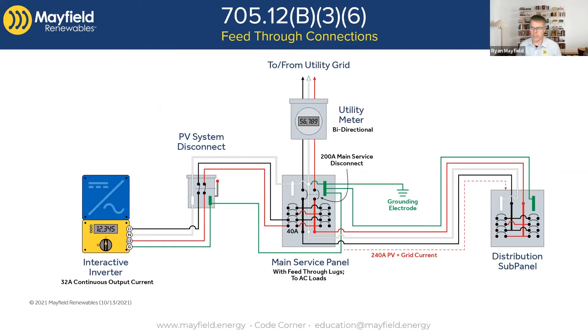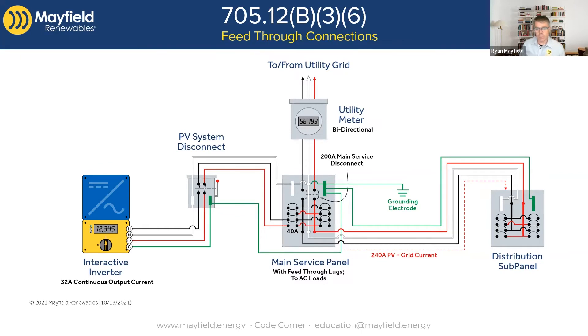Looking at the image, we have our main panel in the middle. There's a PV system coming in and making a connection on a 40-amp breaker, and then there are feed-through lugs that go downstream to an MLO — main lug only — panel that is distributing most of the loads in the house. We have to be aware that when we make this connection using this 40-amp breaker, we now have two sources of power on that feeder going downstream to the distribution sub-panel.